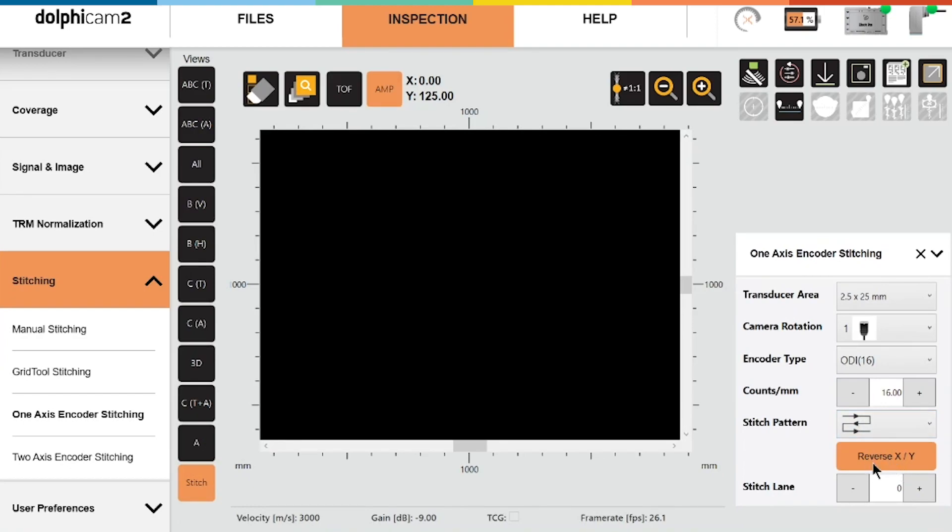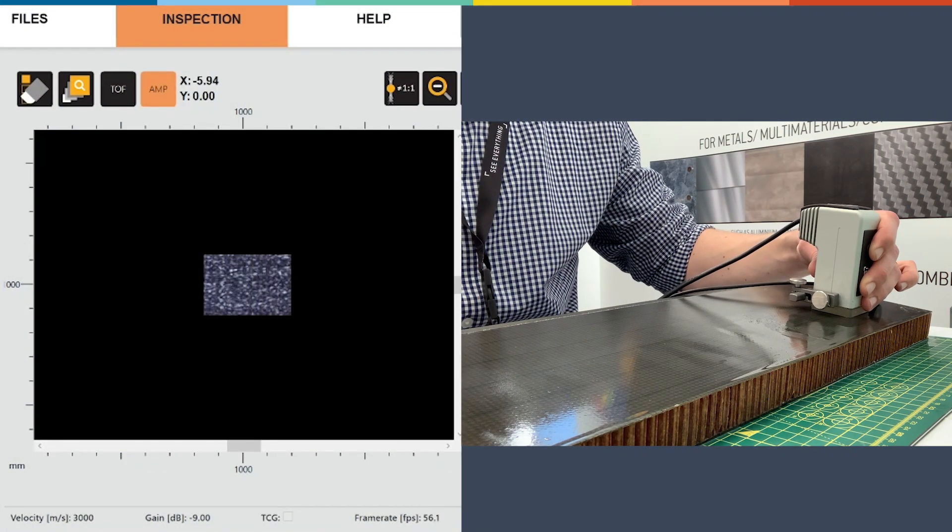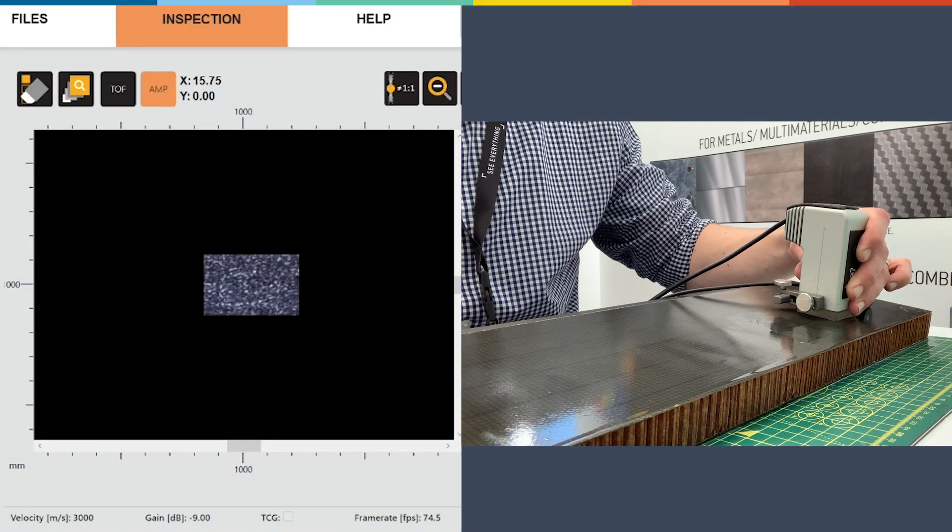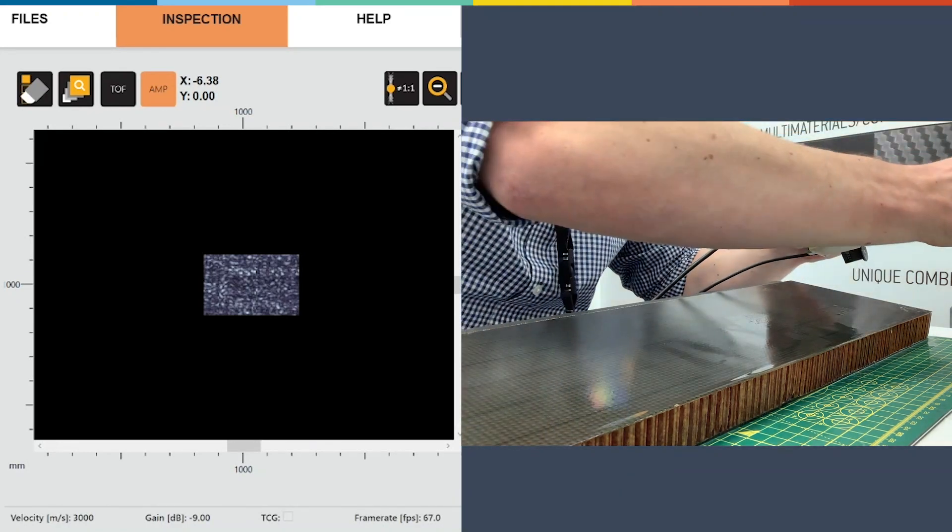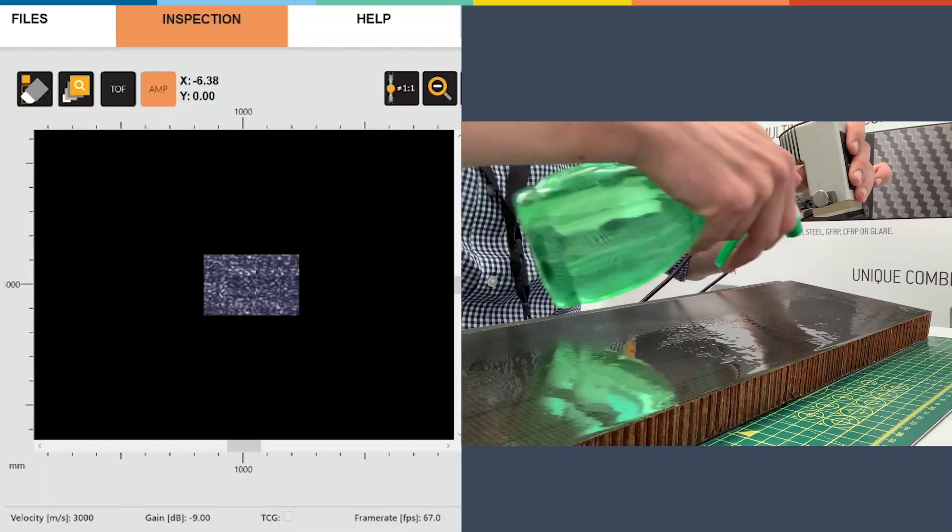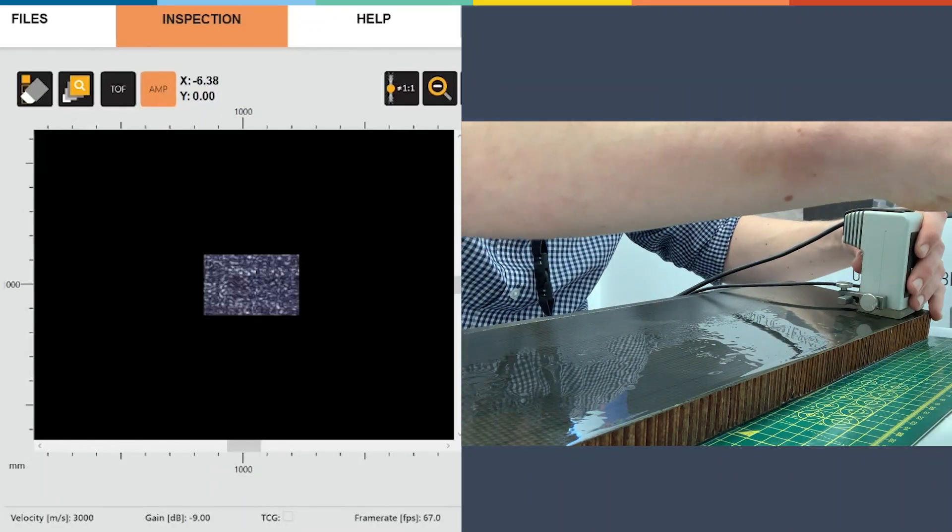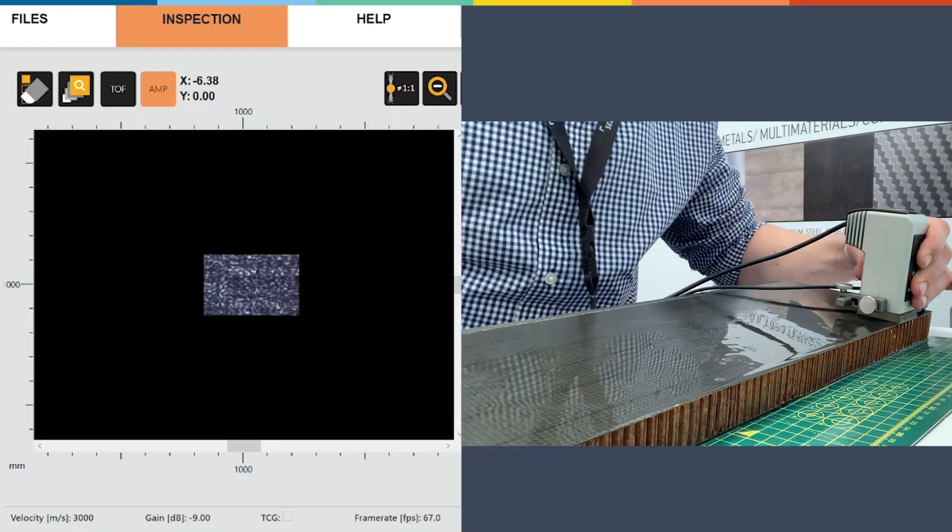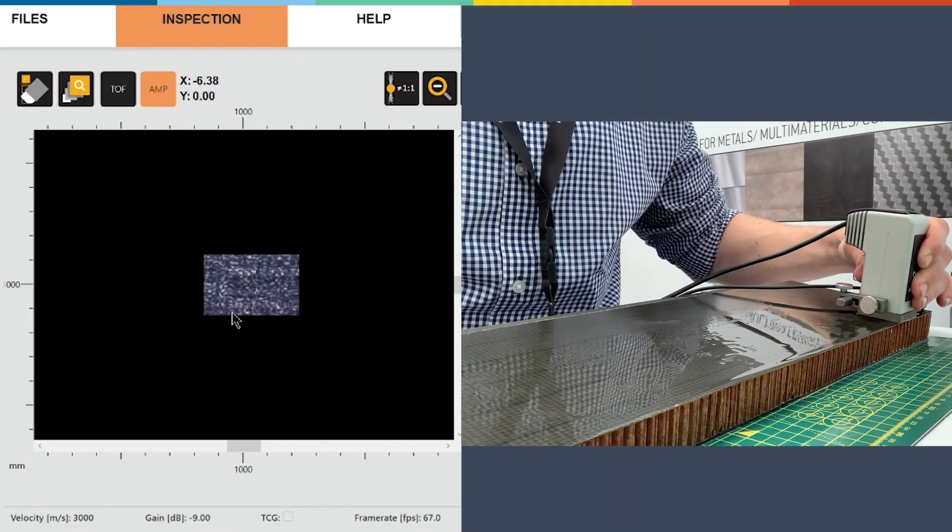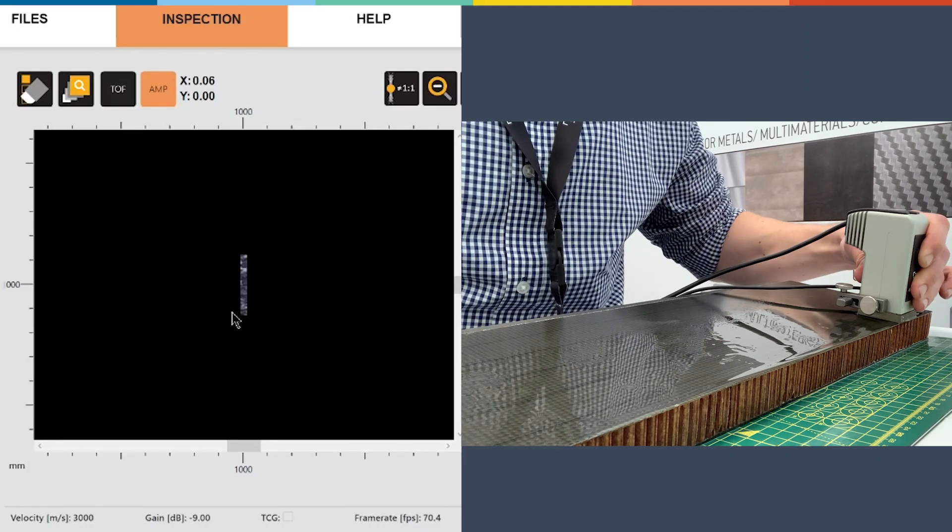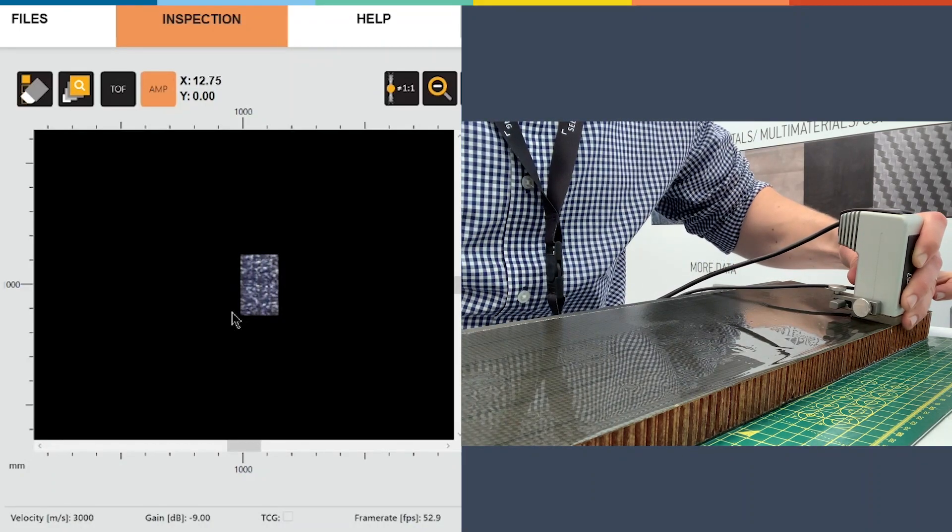We have this reverse XY button if we need to change the direction. We can see it's moving correctly in line with the TRM. I'll start off in the top left hand corner. I'm just using water as a couplant today. I'll clear the current stitch, press the button on my TRM and I'm good to go.